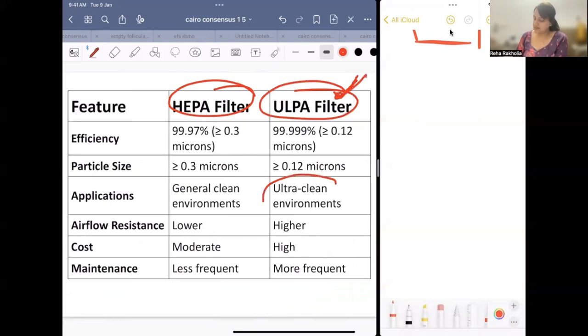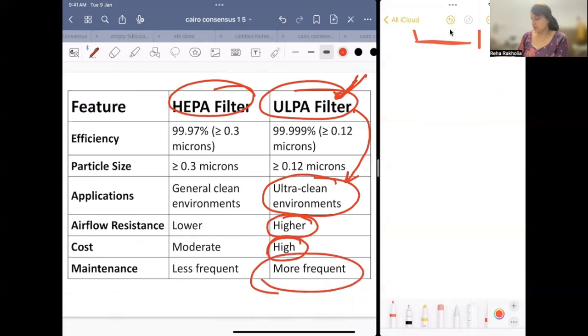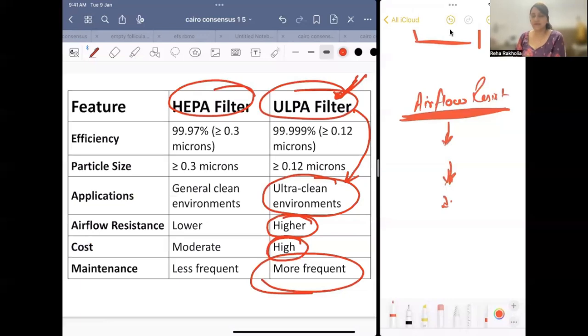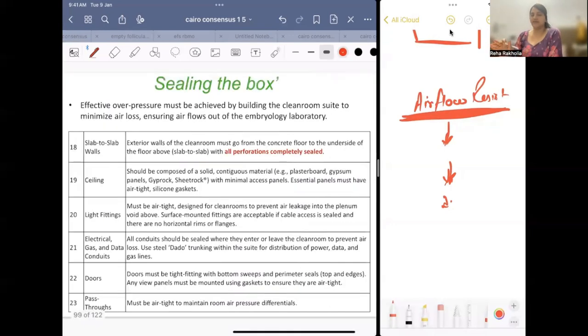Okay, ULPA provides an ultra clean environment. Airflow resistance is higher, and cost is also high, and maintenance is more frequent. Okay. Airflow resistance is higher means what? It means it does not allow all the air to pass. So resistance is higher. It blocks the impure air and passes only clean air. It will consume more electricity also. The cost will be higher also, but it has more efficiency than a HEPA filter, but most of the laboratories use HEPA filters.